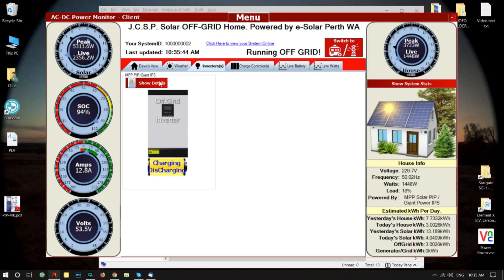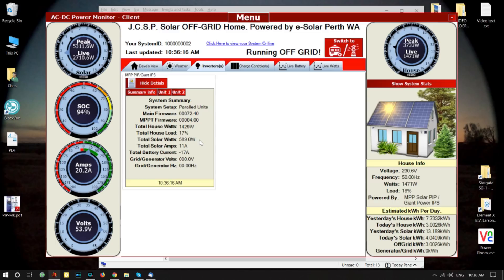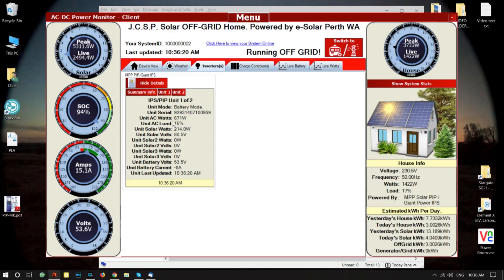And then there are the inverters of course. This is the summary page where everything is combined — we're taking 18 amps from all the solar controllers feeding the loads, and the leftover amps are going into the batteries. You can see the current house load watts right now. That's going to unit one — you can see the AC watts for unit one, solar volts, and batteries. This unit says it's pulling 9 amps from solar.